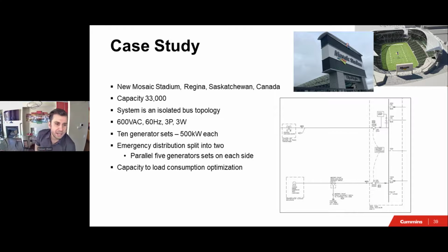Like I promised, there's one case study. I was fortunate enough to go visit that site. This is the new Mosaic Stadium in Regina, Saskatchewan in Canada. It's a stadium that can house 33,000 people. It is 600 volts. They split this into 2 sections, as you can see from the stadium here. So they have 5 generators that can feed power to half the stadium, and the other 5 gensets for each side. So every 5 will parallel together. They just wanted to parallel the generators, and they wanted to have capacity for load consumption optimization.